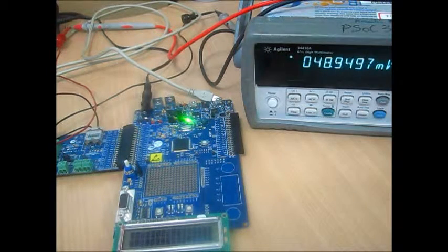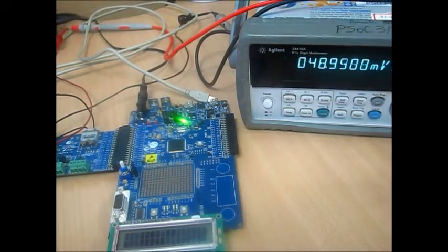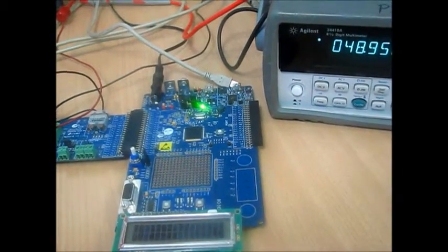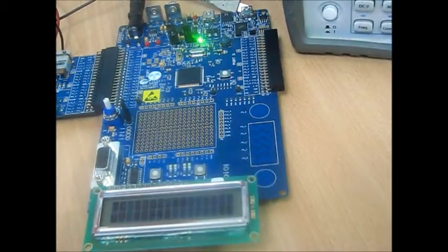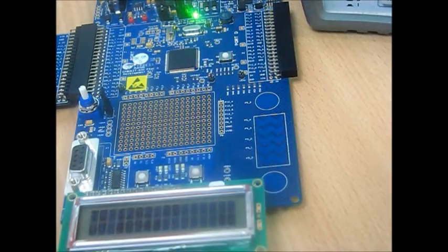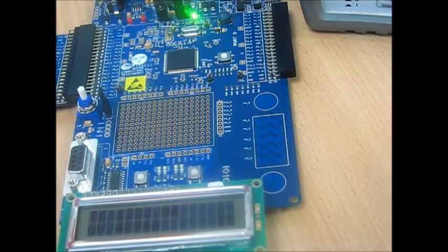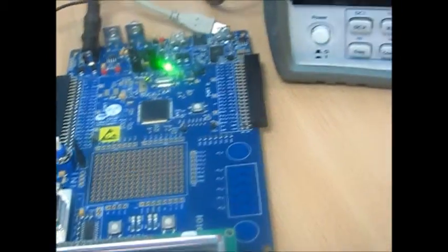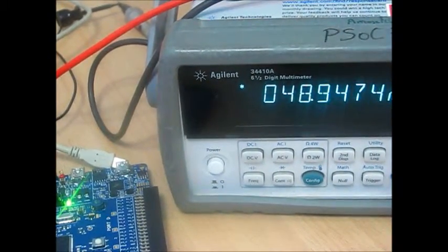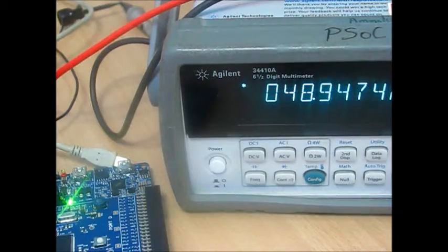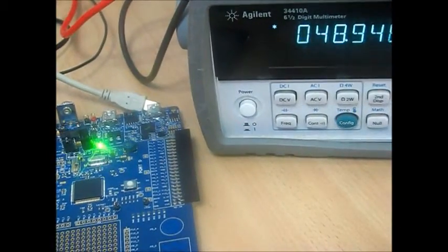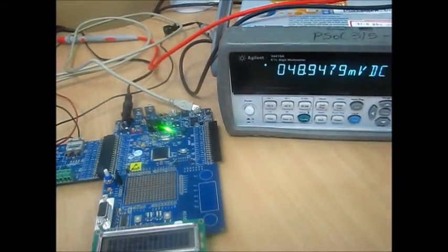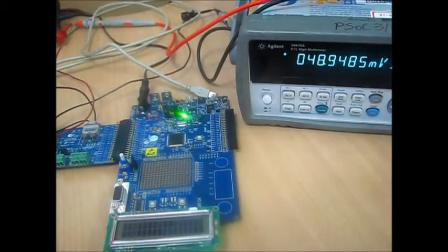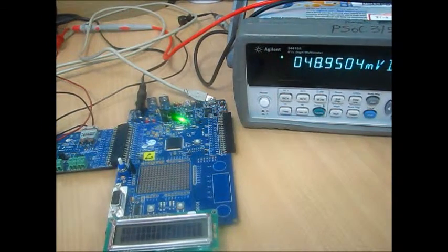So here we see the calibrated accuracy. The PSOC shows 48.945 millivolts, and the standard source shows something similar, 48.946 millivolts. I'm just going to focus both of them in the same frame, and we see that the voltages are very close to each other with a difference of approximately 4 microvolts at the maximum.